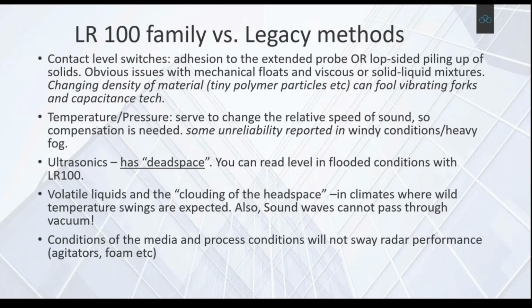As you can imagine, that lower liquid level would boil off because that liquid has turned into a vapor blanket, and it's got to go somewhere, but it's stuck in that headspace. The process conditions, the media itself - I mean things like agitators in there, foam, so there's really foaming levels at startup. If you're doing acetic acid, for example, the radar isn't usually bothered and it will hit through the foam and reflect off the actual liquid level itself. But I would say you'd need to position that with caution, run a few trial runs and learn where your echoes are, where your signals are, and how they correspond to conditions in the tank.